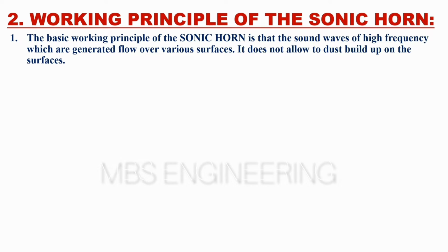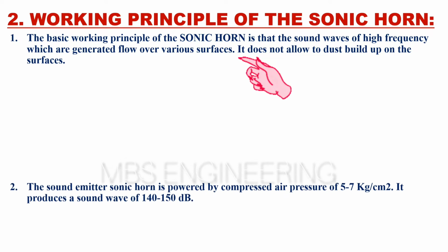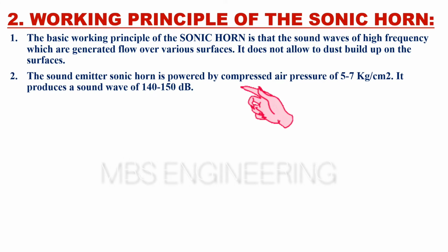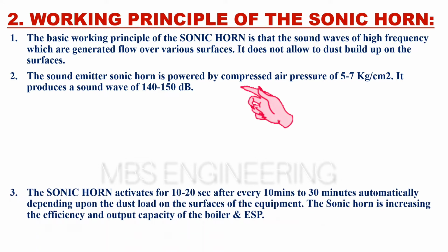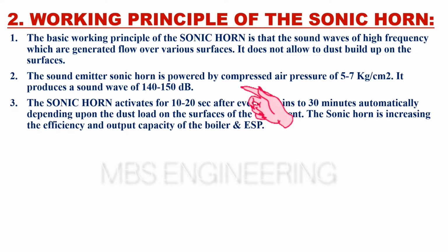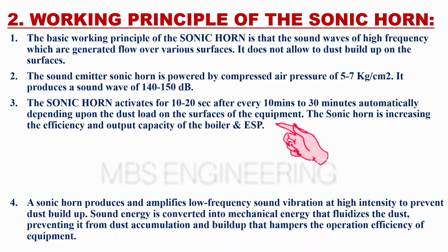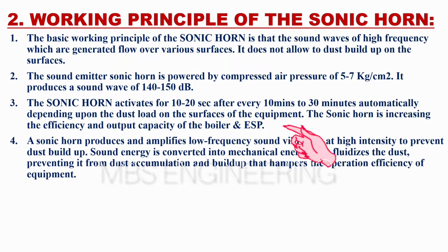Next, we learn about the working principle of the sonic horn. The first point, the basic working principle of the sonic horn is that the sound waves of high frequency which are generated flow over various surfaces. It does not allow dust to build up on the surfaces. Next, the second point, the sound emitter sonic horn is powered by compressed air pressure of 5 to 7 kilograms per centimeter square. It produces a sound wave of 140 to 150 decibels. Next, the third point, the sonic horn activates for 10 to 20 seconds after every 10 minutes to 30 minutes automatically depending upon the dust load on the surfaces of the equipment. The sonic horn is increasing the efficiency and output capacity of the boiler and ESP.